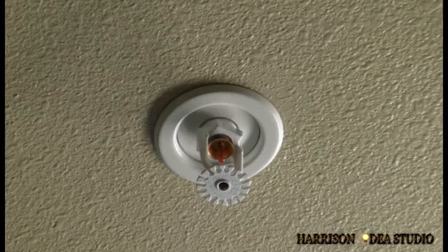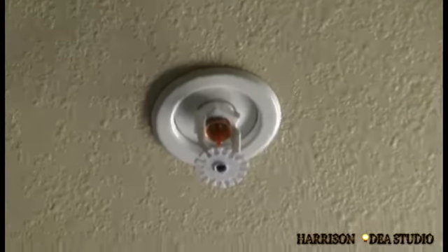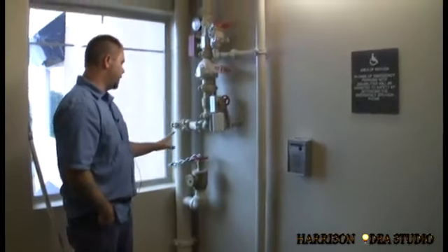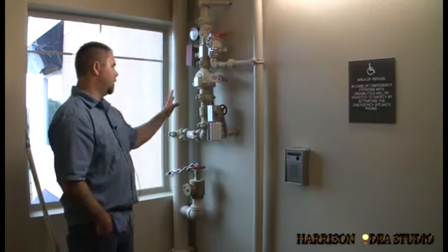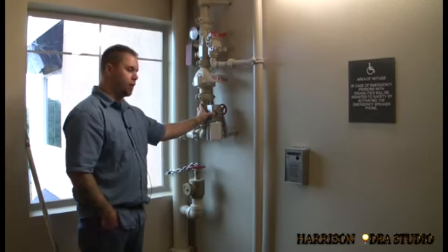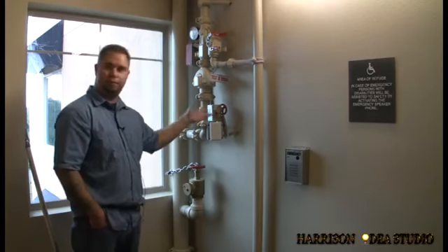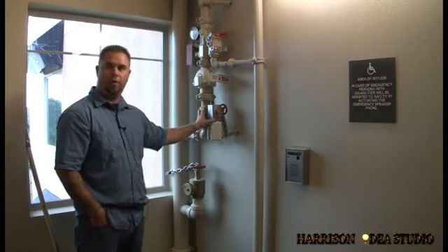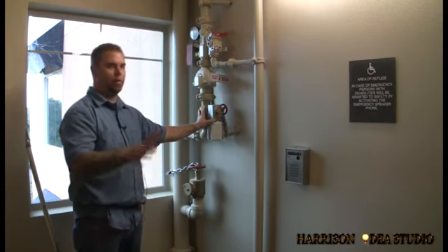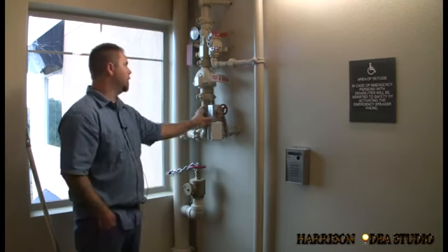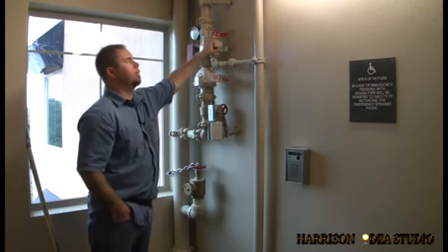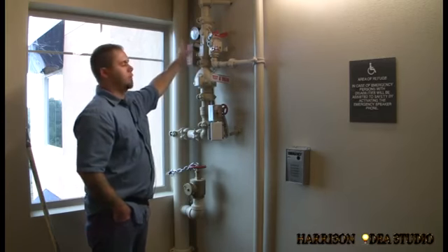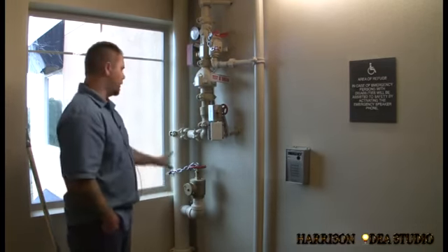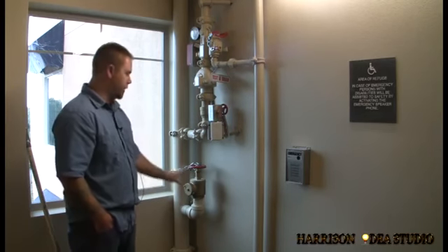All right. And this is what you just went through with us here and behind you. Yes. That's typical of each floor, right? Yeah, the assembly you see here is typical of each floor. Every floor will have its fire department hose connection, a floor isolation valve that's monitored. So if somebody comes in here and turns it off, kids are in here messing around, it'll let the panel know that it's shut. It won't go into alarm, but it'll give you a supervisory signal. And your check valve and your riser manifold, your main drain and test drain, your flow switch and your gauge. Every floor is very typical. Orientation might change a bit, but the general setup is all the same.